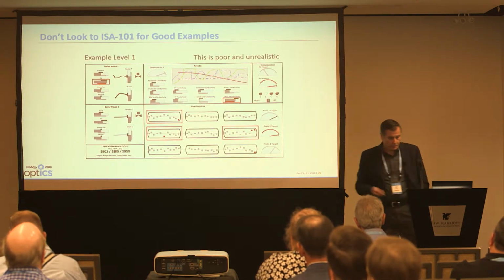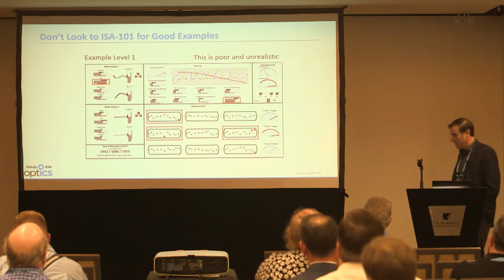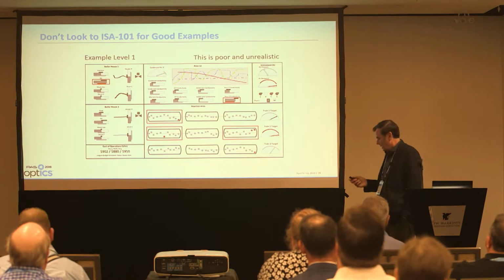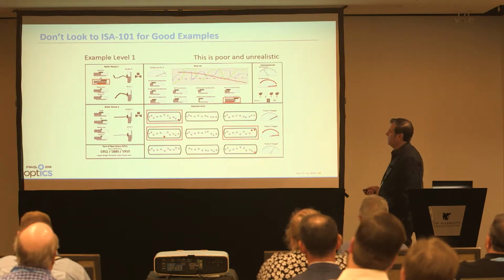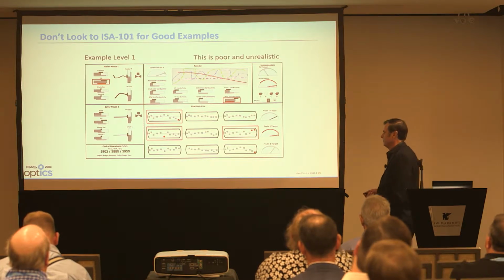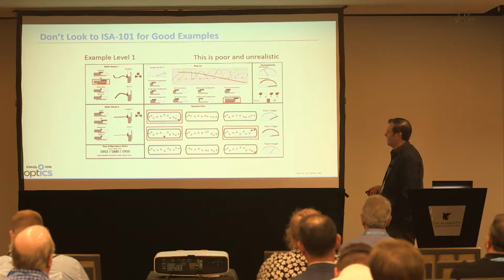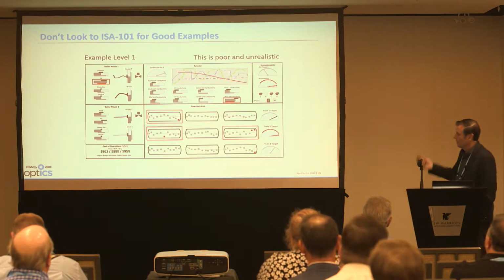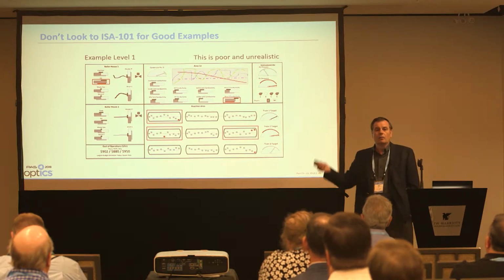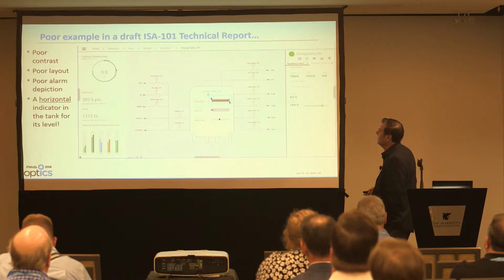Now, you might say, well, we have a standard. It's called ISA 101. Surely we have some good examples in there. No, we don't, and don't call me Shirley. This is an example in ISA 101. They were intentionally, frankly, kept not so good. But this is not worthy of being called a level 1 graphic. It's unrealistic. The point is you can't look to the ISA 101 standard for examples of good graphics. They are not in there.